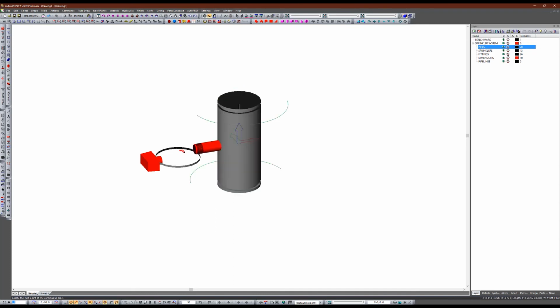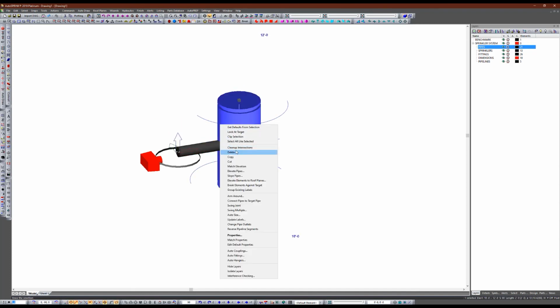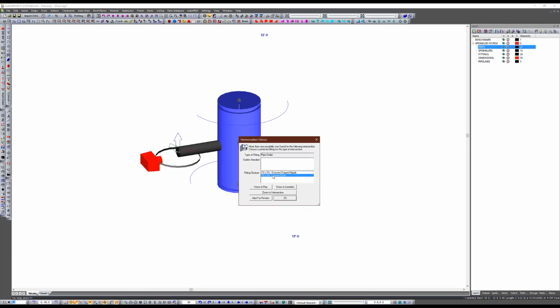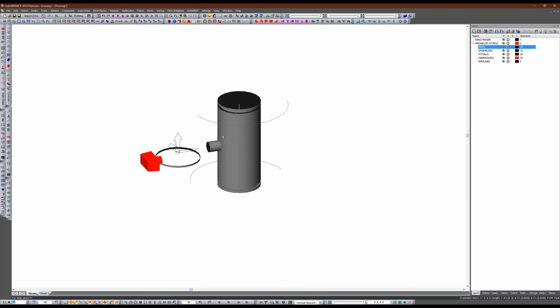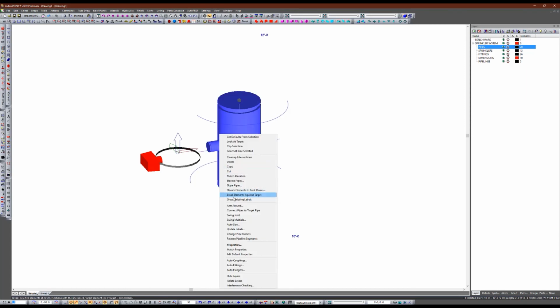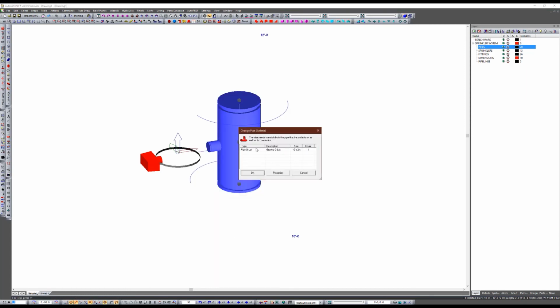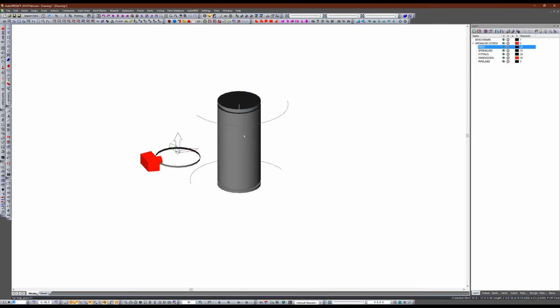I'm just going to draw a piece of 2 inch coming out of the side here to get an outlet, which I will then change. Delete that temporary pipe. Right click this, change pipe outlet. I'm going to change this 10 by 2.5. Why in the world did I put 2.5? I don't know. I could have sworn I drew a 2-inch pipe. But I want to change this to a pipe to pipe outlet, pipe weld hole, 10 by 2. Okay, now I've got a pipe weld hole that I can snap this flow switch into.